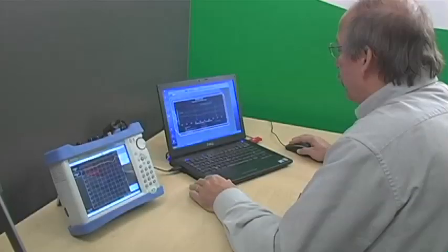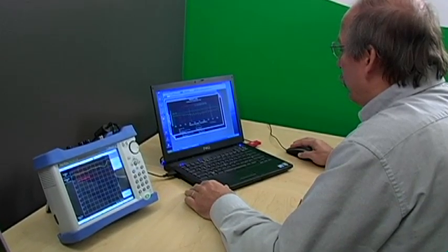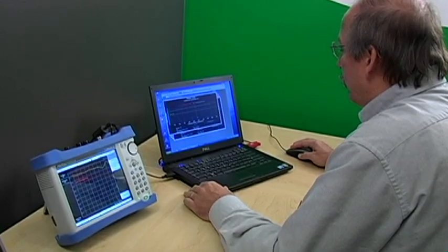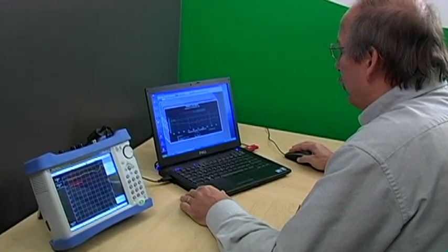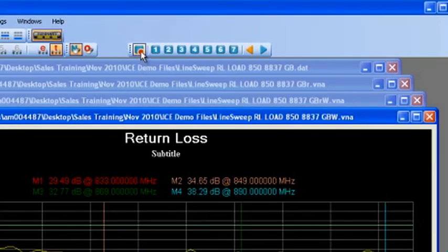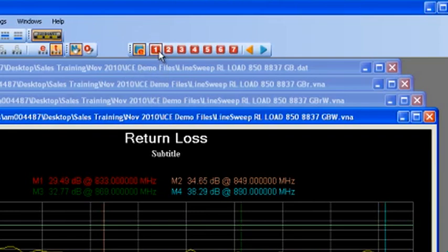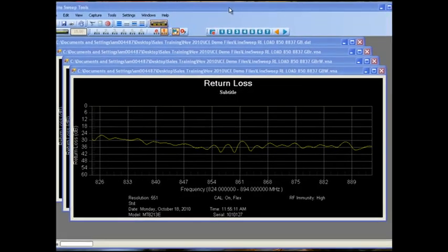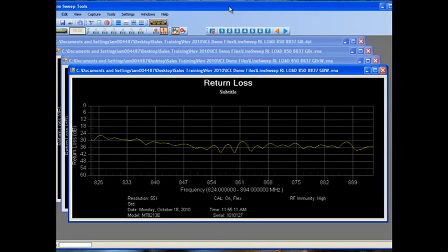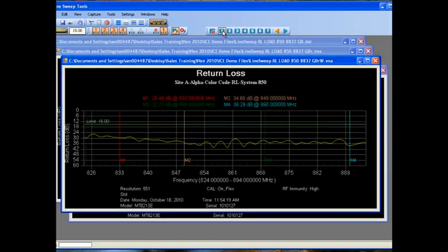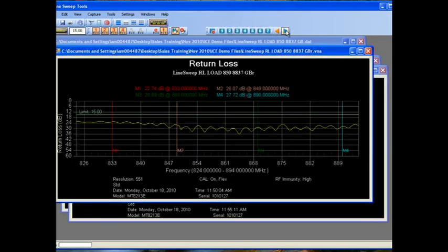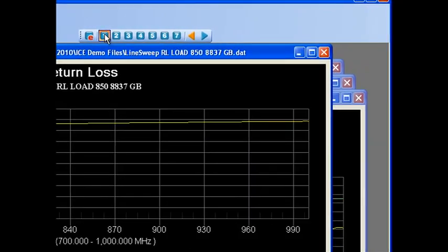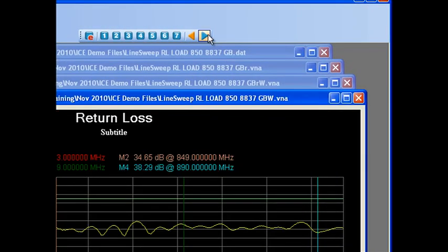Presets: When working with dozens of traces, it's handy to have quicker, accurate methods to set limit lines and markers. Presets makes this job quick. To create a preset, press the Edit Preset button. The presets turn red, and by clicking on Preset One, we can save the current marker and limit line setup. Now press the Edit Preset button again. The presets turn to teal and are ready to use. In this example, there are three similar return loss traces open. Click on Preset One to set up markers and limit lines for the first trace, click on the Next Trace button, and set the same preset on the second trace, and so forth. With up to seven presets available, reviewing traces for proper markers and limit lines can be done very quickly.